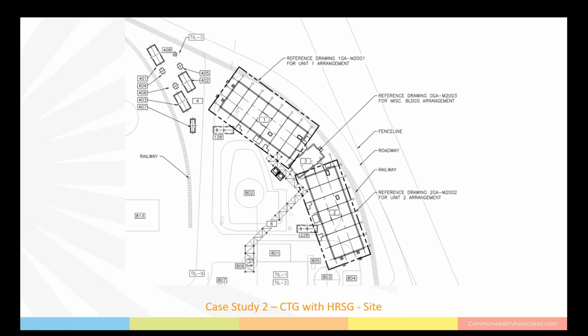The client, let me go back to the fuel. They do have fuel on site, but it's not near the location for the new CHPs or at the correct pressure. So we had to bring gas in from a different location. We compress it in the gas yard, which is item 4 in the upper left corner, where we have gas compressors, aftercoolers, and a knockout drum.